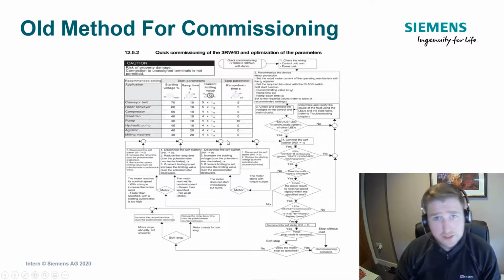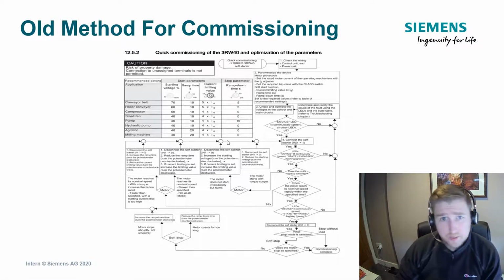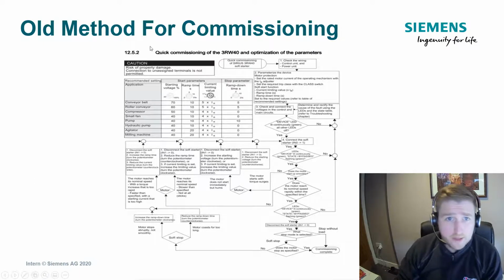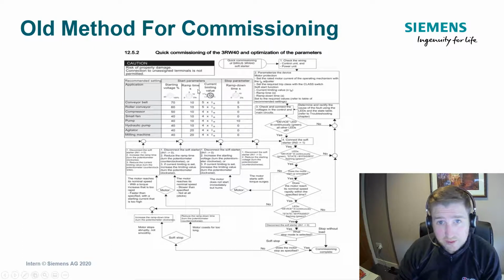On this next slide, I just wanted to show you in the user manual the older operation for connecting a 3RW40 in terms of its commissioning process. The old way is you'd have a look down this list, and it'll give you a few suggestions dependent on what you'd set those pots to. These only cover 4 of the pots. There's 5 pots on there. There's one that is missing in terms of the overload, so you don't know what to set the overload to with this graphical representation. But it gives you a rough idea of what you might want to set those pots to.